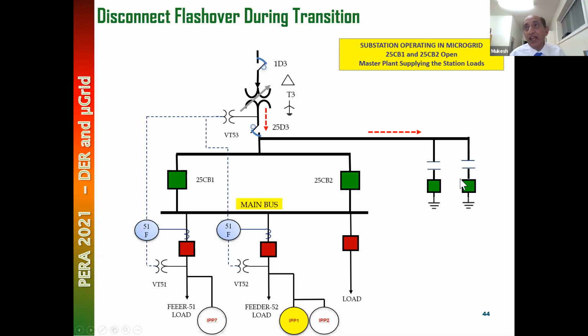So what happened? There was some SCADA mistake. There are these capacitors here, and the indication of these capacitors was incorrectly sent to the control room. They were showing these breakers are open. Actually, they were closed. So there was a current flowing like this. See, these breakers are open, and there was a current flowing here. And no one was checking the current. They just saw the status of this is closed and this is closed. Control room did not have a recording of current flowing here. Only they had indication that these two breakers are closed.